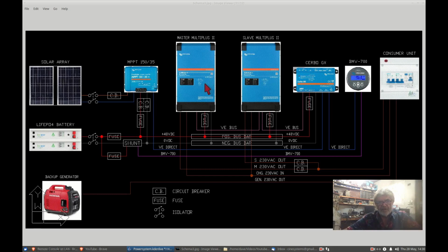Now on the main side, the 230 volt side, we have each output, each inverter coming down to an independent circuit breaker. They're common on the system side and then disappear into the consumer unit here. The backup generator. So we have a backup generator which can be used either just for charging or for power assist. So if I need a few more watts out of the inverters, I can fire the generator up and it will assist the power. So it disappears into the consumer unit via a circuit breaker, comes back out. There's a double power point and then a lead that goes into each inverter. So that's a basic rundown of the system.